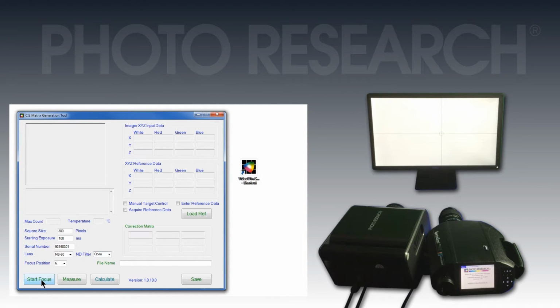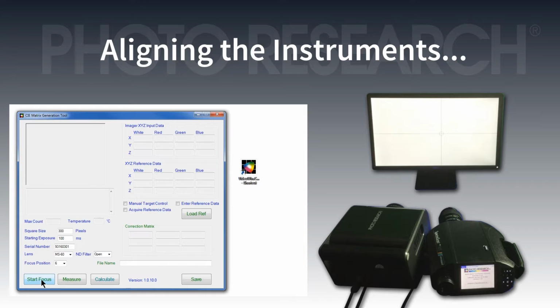Once the setup is complete, point the imager at the target and click Start Focus. Move the imager so it is looking at the target and adjust the lens until it's in sharp focus. When that's done, click on Stop Focus and enter the focus position. Next, make sure the spectroradiometer is pointed at the same spot on the display and at an angle as close as possible to that of the imager. Moving it back if necessary will help this.